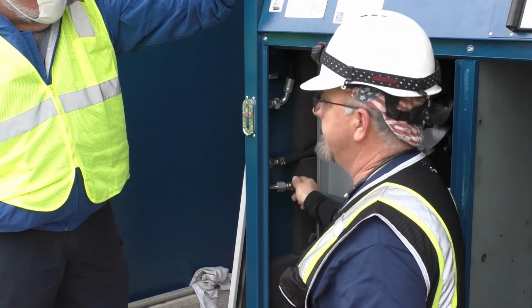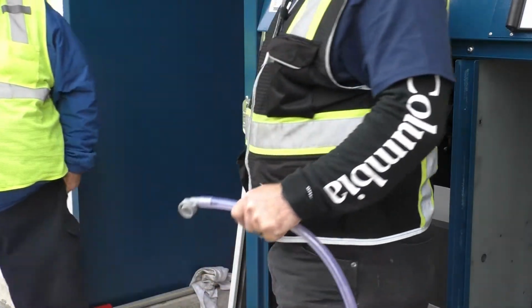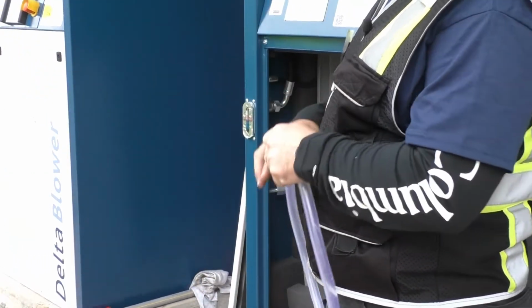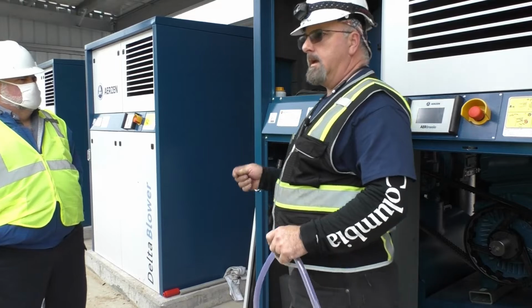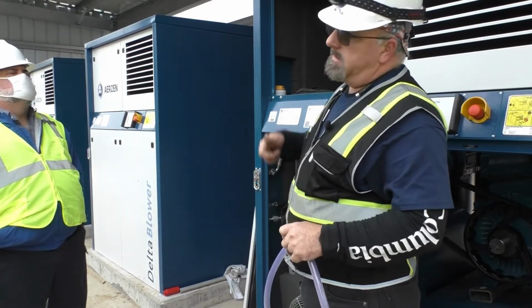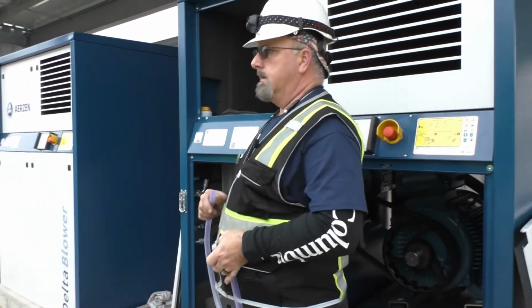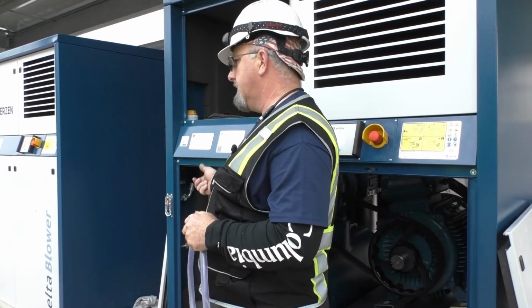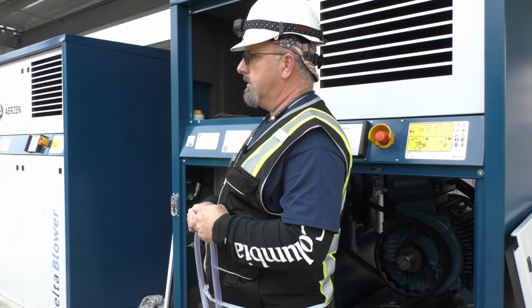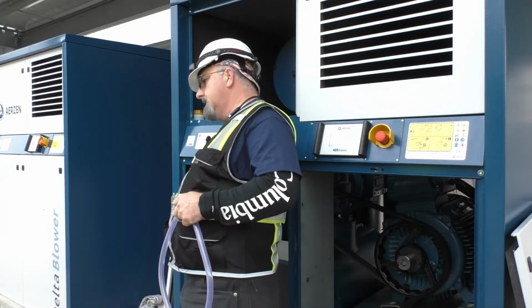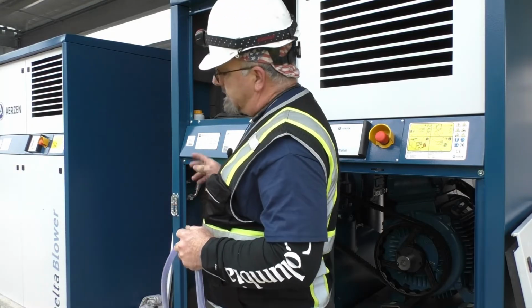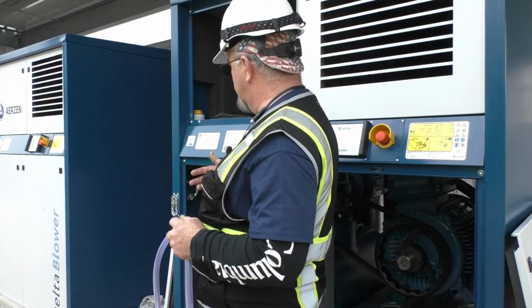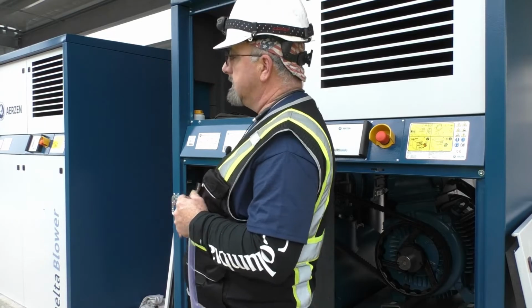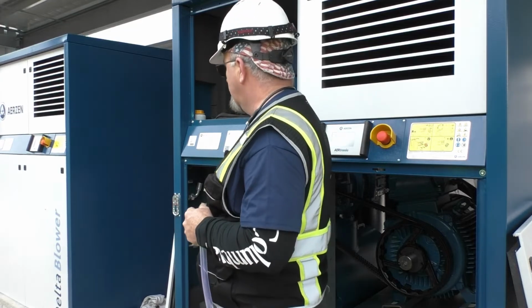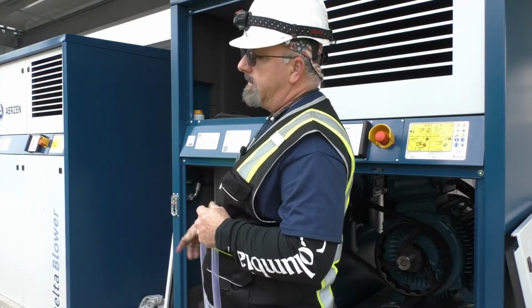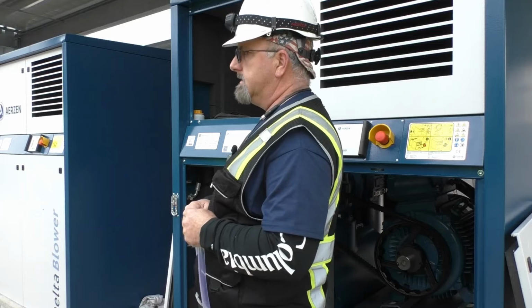And like I said, hand tight. If this valve sticks or fails and does start seeping around this cap, you can tighten it up a little bit, but just really wrenching down on it is not going to help. Just over hand tight is about as tight as you'd ever want to go with it. If that valve does stick, you can change it out without having to drain the oil. But if that starts leaking or fails, you will have to drain the oil out to change that out.